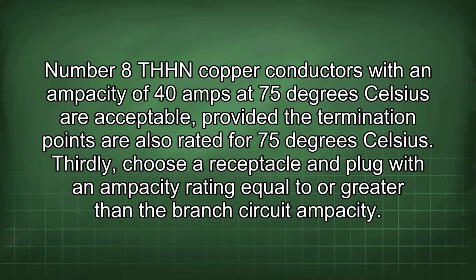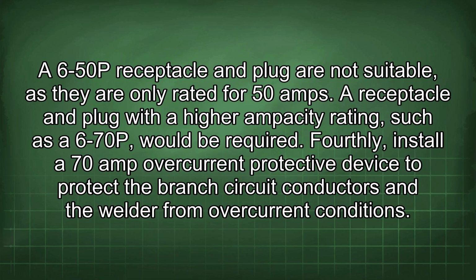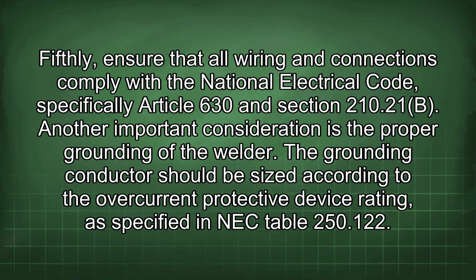Thirdly, choose a receptacle and plug with an ampacity rating equal to or greater than the branch circuit ampacity. A 6-50P receptacle and plug are not suitable, as they are only rated for 50 amps. A receptacle and plug with a higher ampacity rating, such as a 6-70P, would be required. Fourthly, install a 70 amp overcurrent protective device to protect the branch circuit conductors and the welder from overcurrent conditions. Fifthly, ensure that all wiring and connections comply with the National Electrical Code, specifically Article 630 and Section 210.21(B).